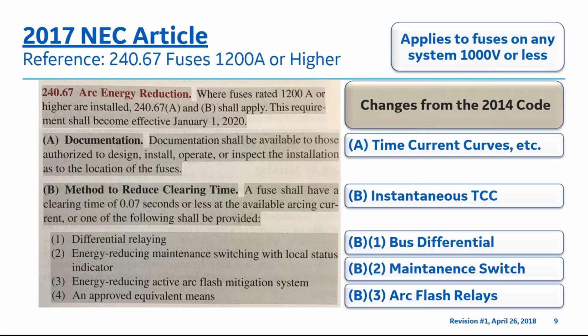The items highlighted in gray are newly introduced items for 2017, which represents this entire article for fuses in the codebook. The first section, 240.67, where fuses rated 1200 amps or higher are installed, 240.67A and B shall apply. This requirement should become effective January 1st, 2020. Paragraph A, documentation. This involves time current curves, which are available on specific manufacturer websites for specifiers.